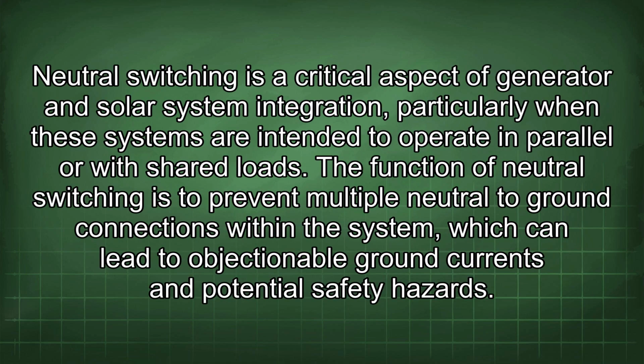Neutral switching is a critical aspect of generator and solar system integration, particularly when these systems are intended to operate in parallel or with shared loads. The function of neutral switching is to prevent multiple neutral to ground connections within the system, which can lead to objectionable ground currents and potential safety hazards.